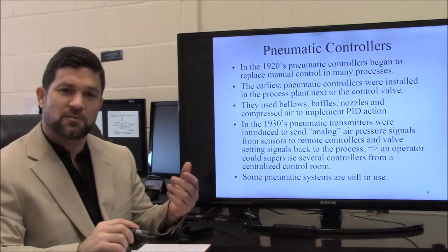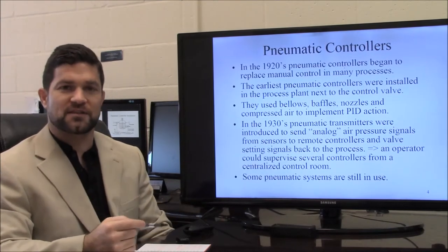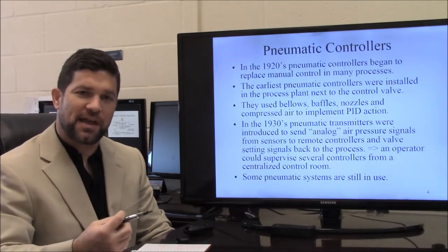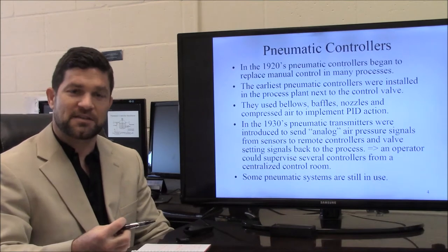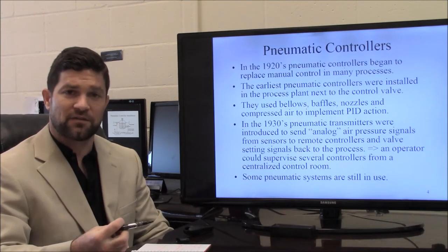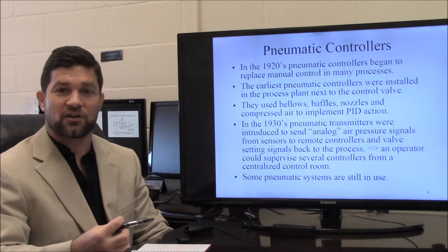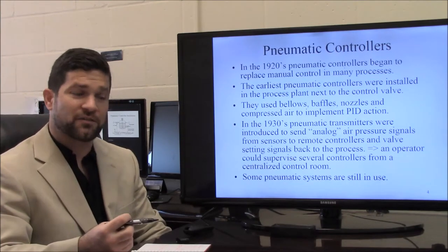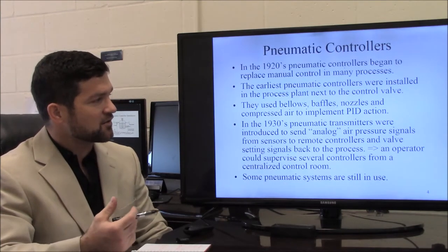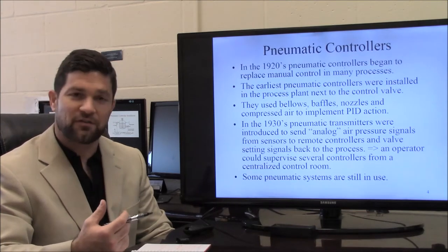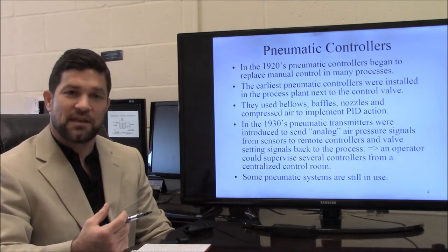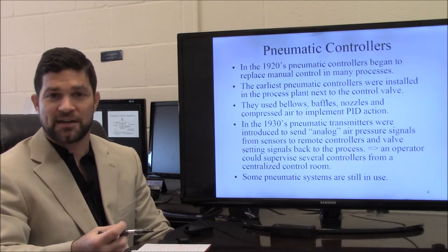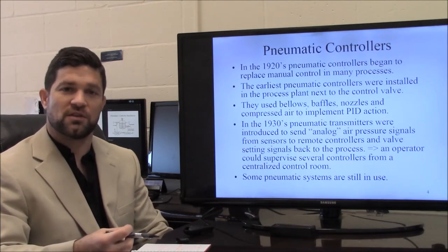Some brief information about pneumatic control systems: the general idea is that we have air that's going to be the signal sent to the valve, and also sent through the entire control process. Air is transported through pipes, it goes to valves, and you have systems that are developed based on bellows, baffles, and nozzles, and they use compressed air to integrate PID or control action into the control loop.